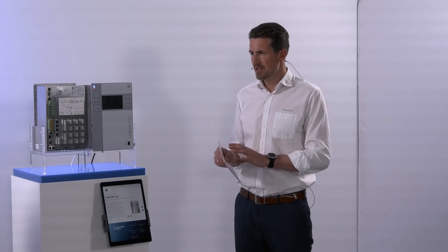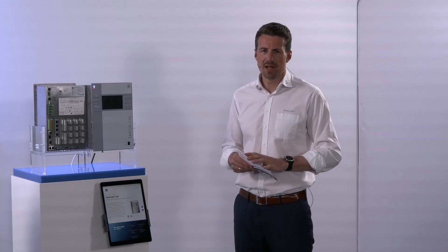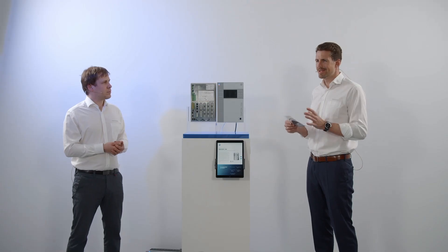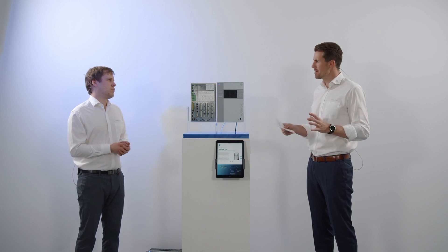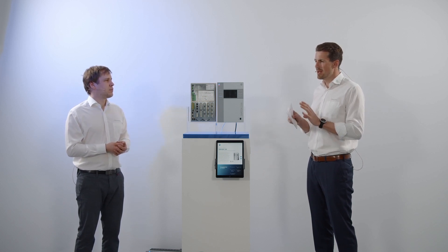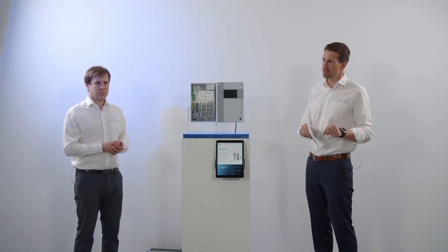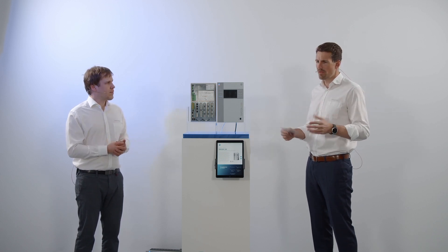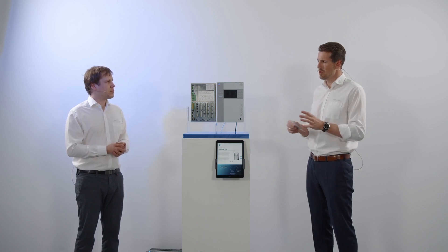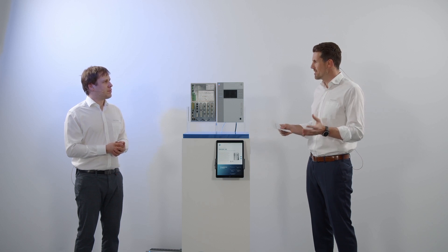Thank you, Peter. That means three basic approaches: we have the TAPCON 230 for all basic requirements in the network; we have the TAPCON ISM, a premium device for special applications; and last but not least, we talk about an integrated AVR function within the ETOS system — the cubicle that operates the tap changer and monitors different parameters on the power transformer — the embedded transformer operating system.